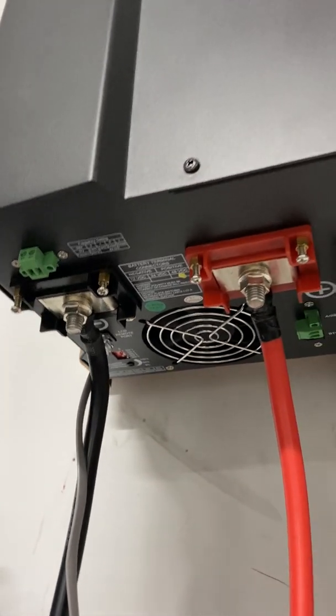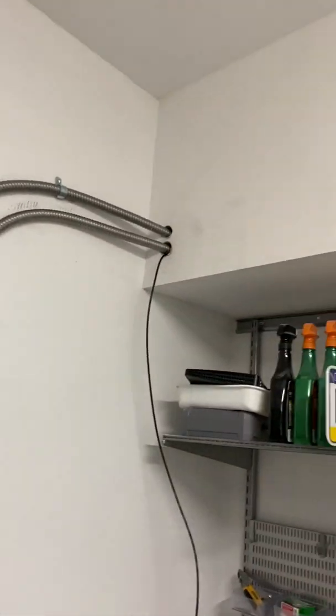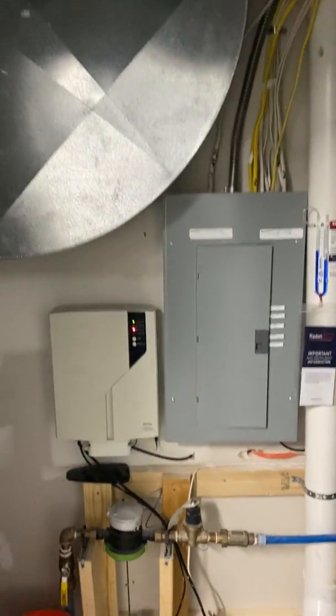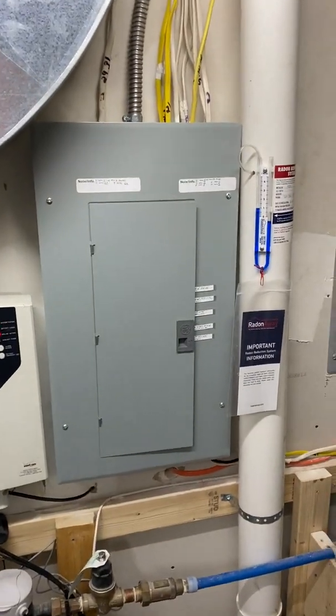I will be covering the dip switches shortly when I shut the power down after the test. As you can see, I've got a 90 amp breaker even though this unit is rated for 75 amps, and then I've got some thick gauge cable that goes all the way up and threads through into my server slash electrical room.